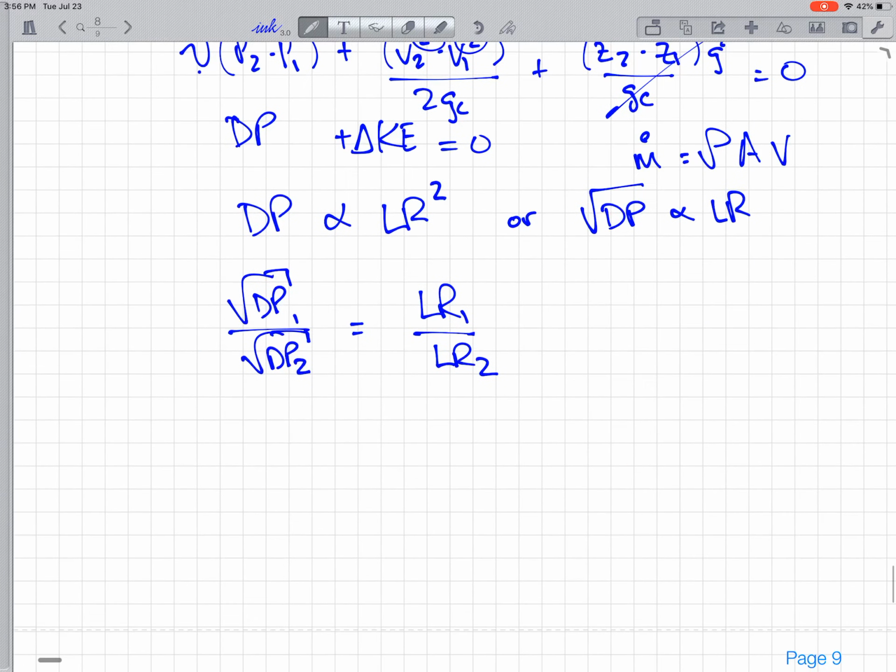And we have a dP of 1, which is going to be 60 psig. That's why I said it was an atmospheric leak. The dP is actually going to be 60 psid, or 75 psia minus 15 psia in the atmosphere. All right, that's one of the advantages of using pounds gauge. So these aren't pressures as much as they are DPs in this case.